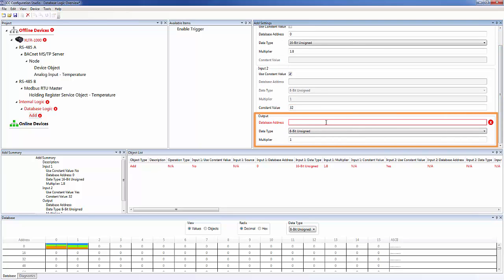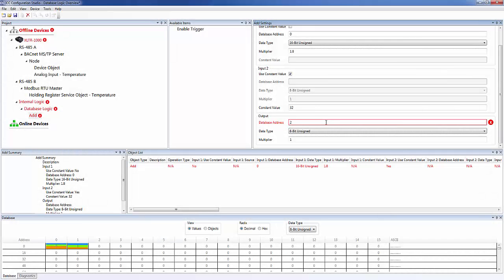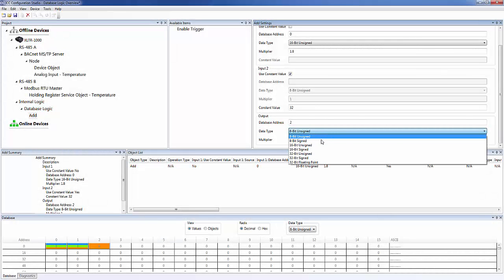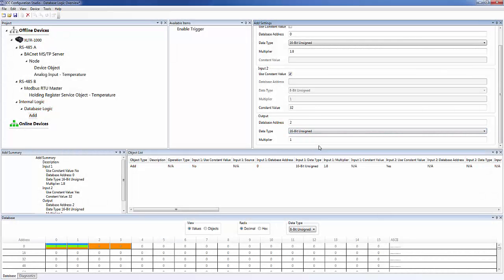Finally, we have to store the result of the operation into the database. We'll use the next available database address, address two. And again, we'll use a data type of 16-bit unsigned. We'll leave the multiplier at one, since we don't need to scale the output value before storing it into the database.